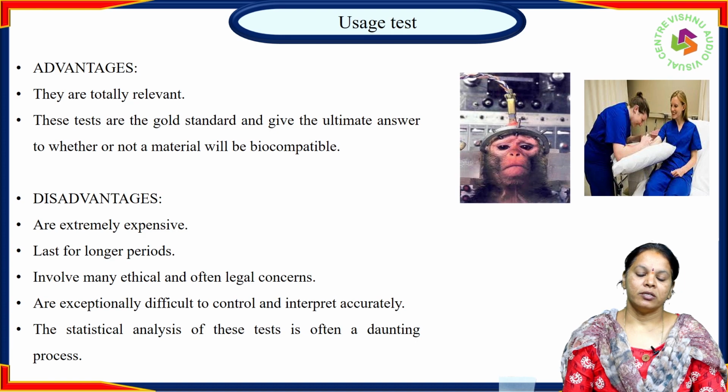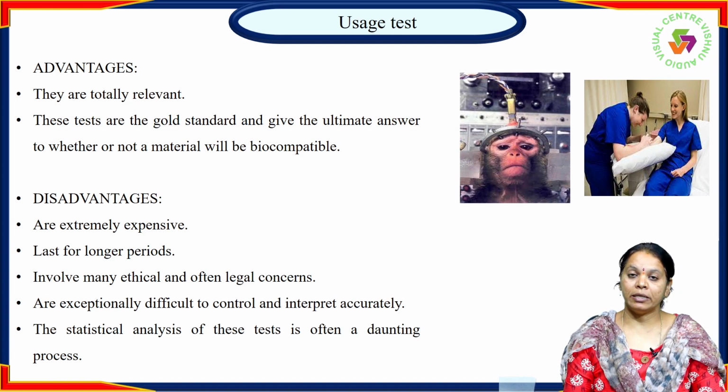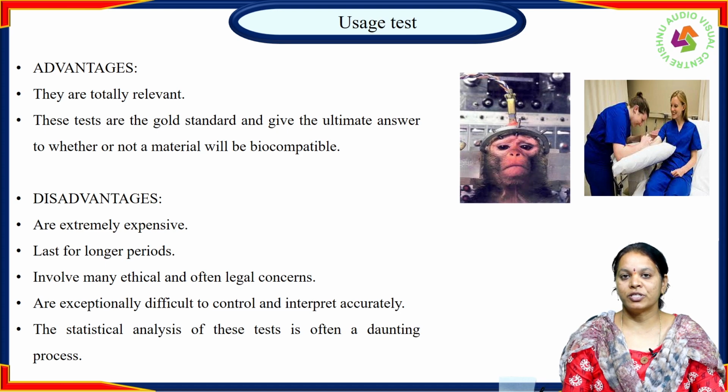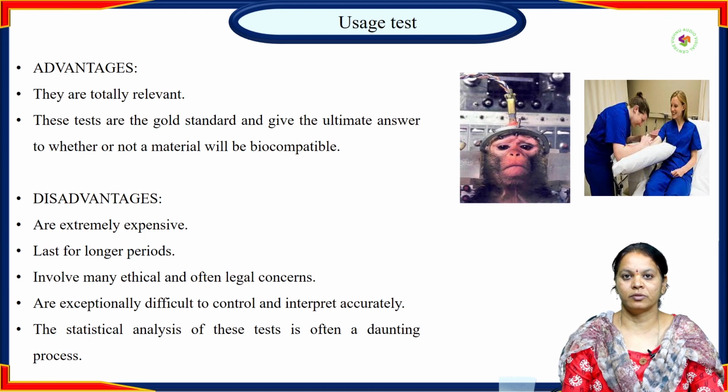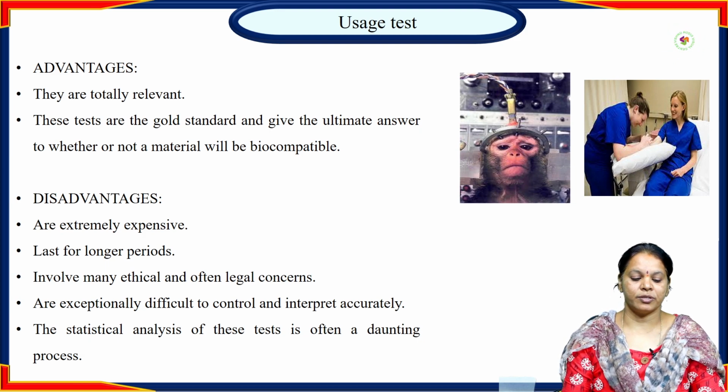The advantage of this test is that it is totally relevant and a must for the commercialization of that product into the market and getting it implanted in patients. So these tests are the gold standard and give the ultimate answer on whether the material is compatible or not. The final decision on its biocompatibility would be given based upon the results of the usage test.